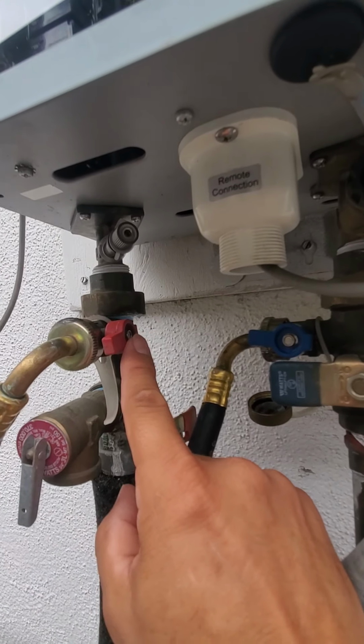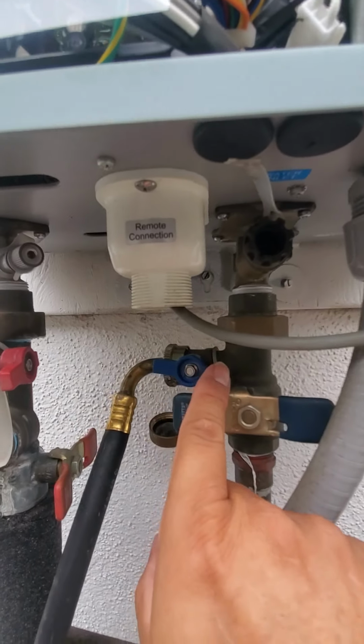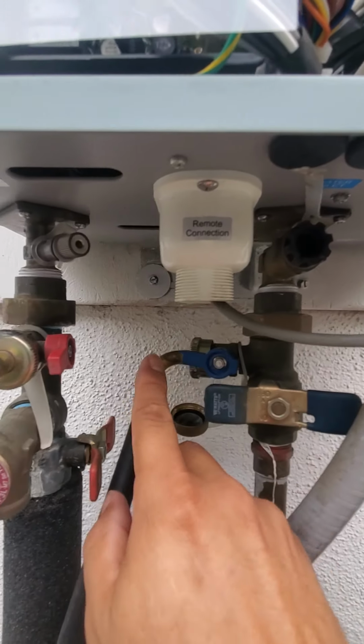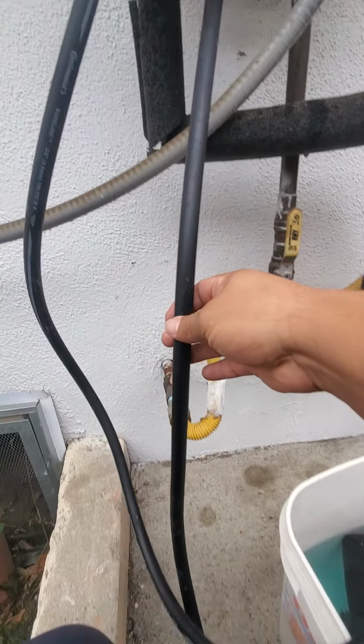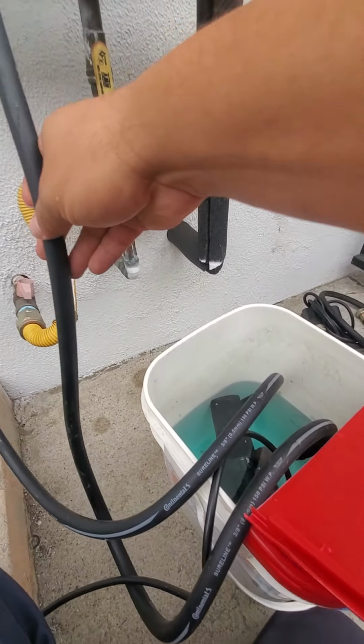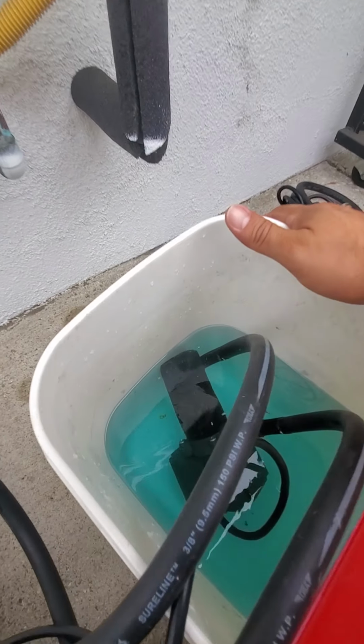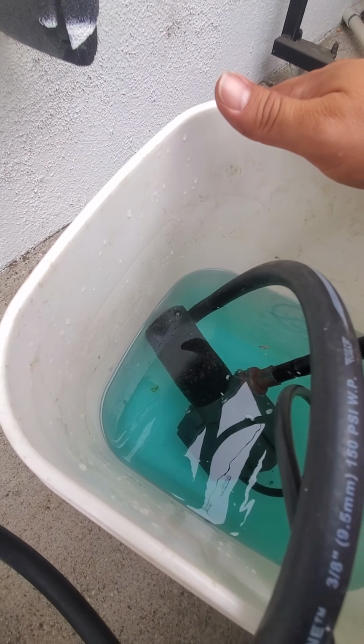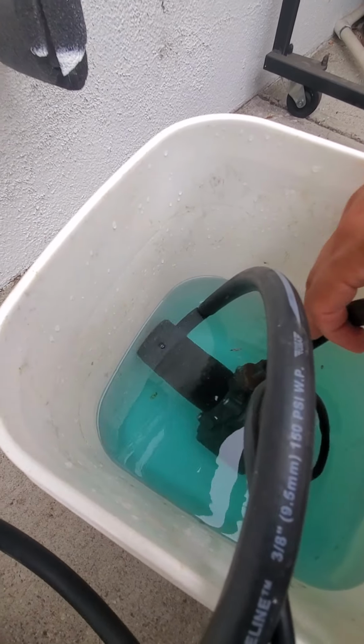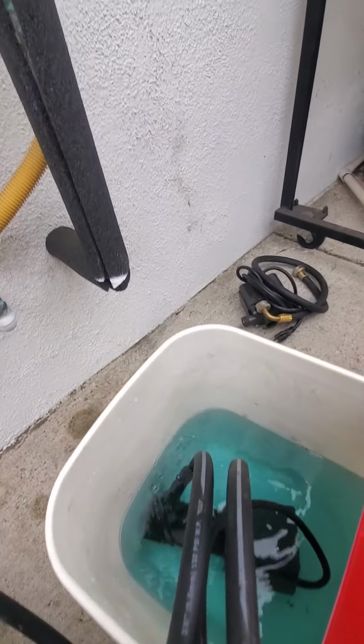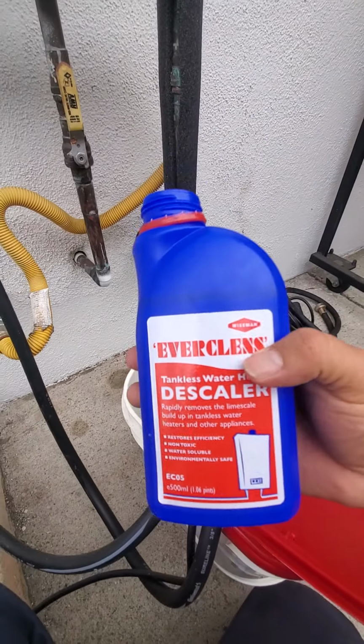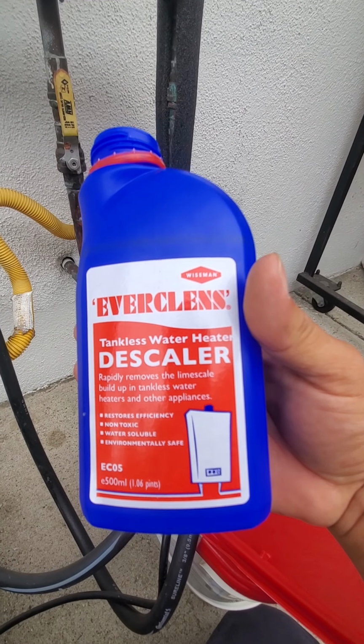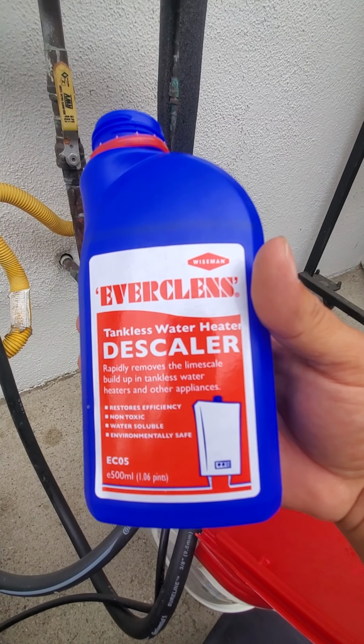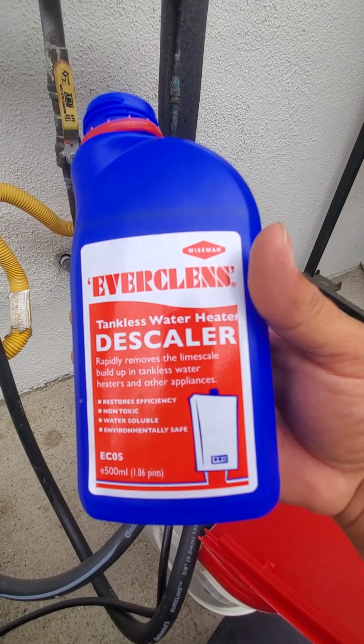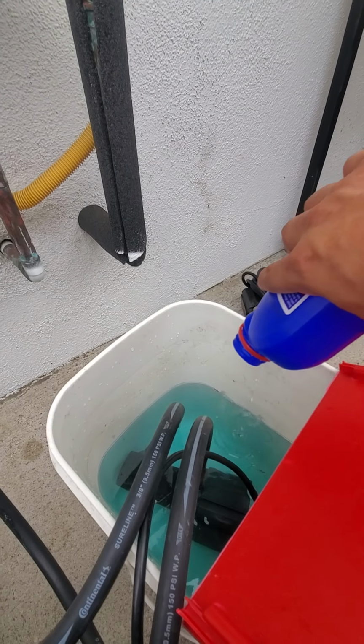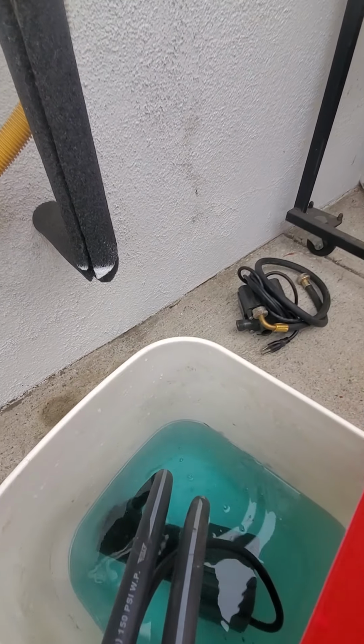We open our service valves right here, the cold service valve, and connect this hose, which leads into this bucket with our little transfer pump. Basically that picks up the water, which uses this descale solution here. This is made by Everclens — it's a tankless water heater descaler solution. You add this in to here like so.